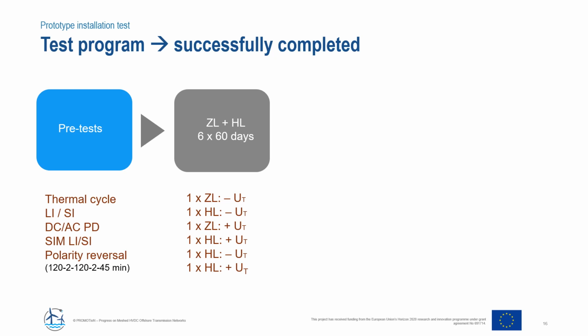So here you see zero load has had 2 blocks, basically corresponding to positive and negative DC voltage. High load has been performed 4 times, twice for each polarity. And at the end of each block, there are also other tests. For example, lightning impulse superimposed onto the DC, and close and open operations of switch disconnectors and earthing switch in that case, and also partial discharge measurements have been involved.